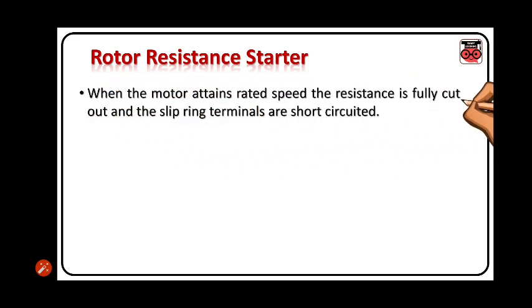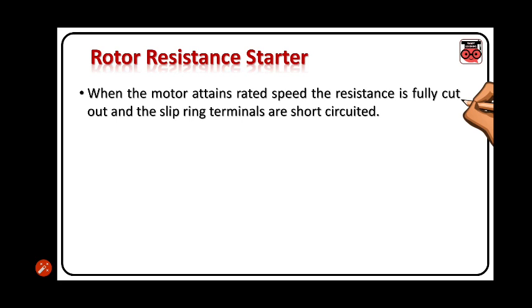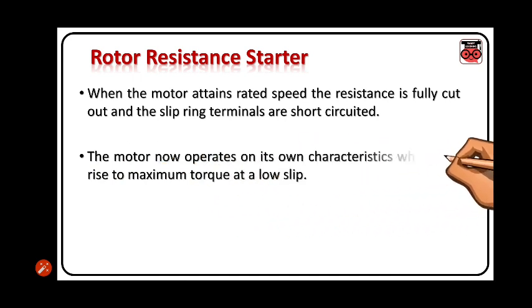When the motor attains rated speed, the resistance is fully cut out and the slip ring terminals are short circuited. The motor now operates on its own characteristic which gives rise to maximum torque at a low slip.